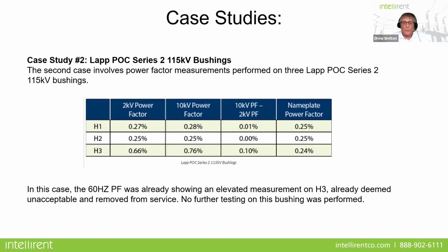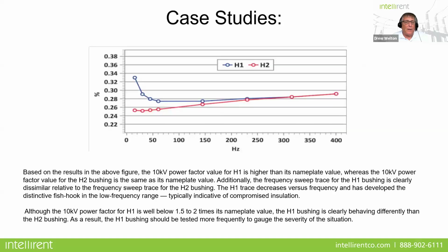On the other two, again, we see kind of within range. Your tip-up test had a little bit of variance on H1. But again, if we look at the variable frequency results, we see that H1 is elevated. That would also indicate that we should take a better look at H1 going down the road.